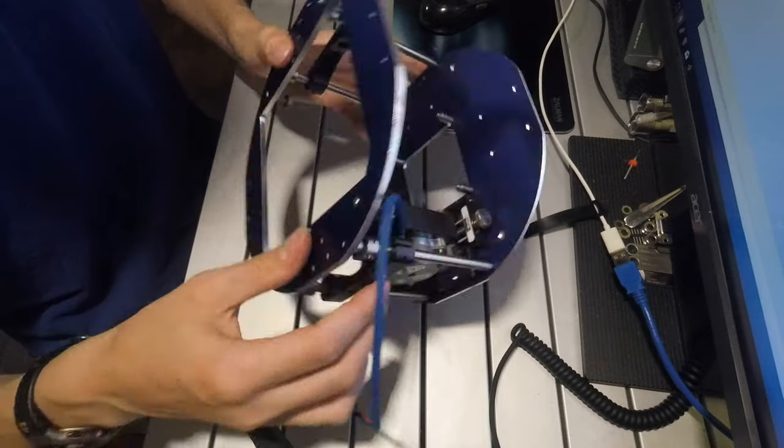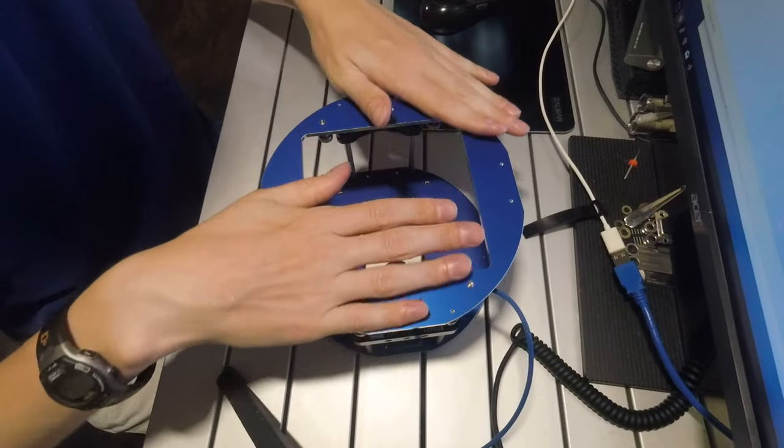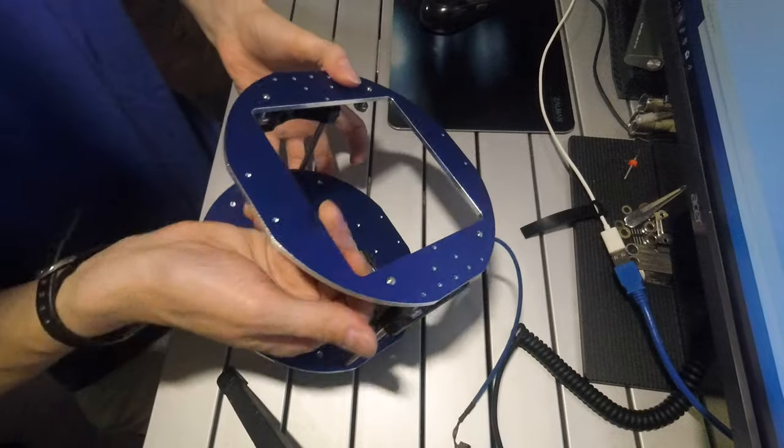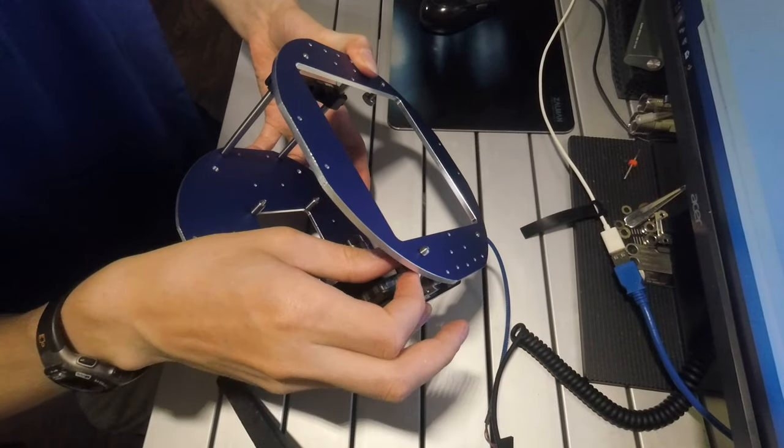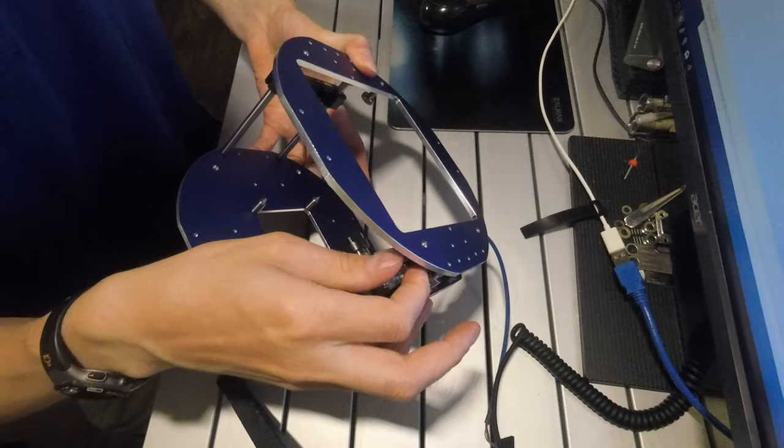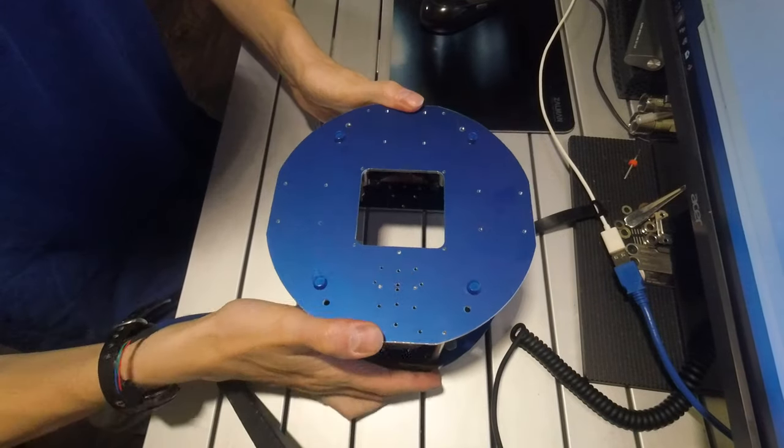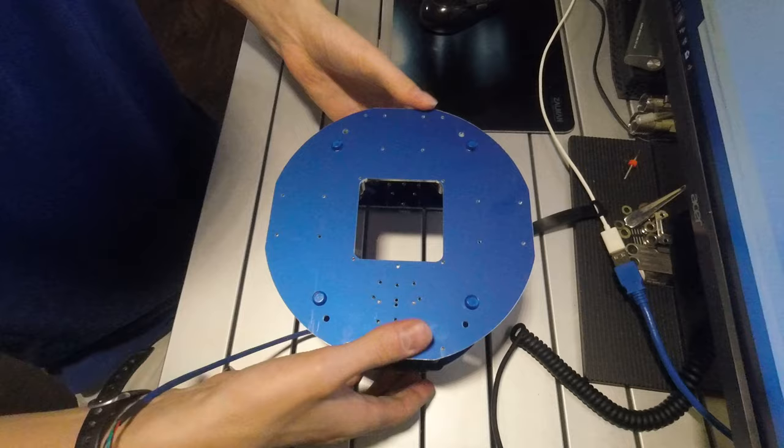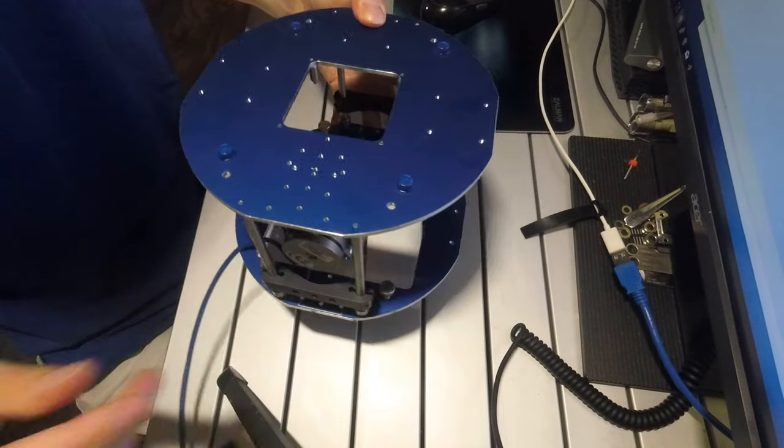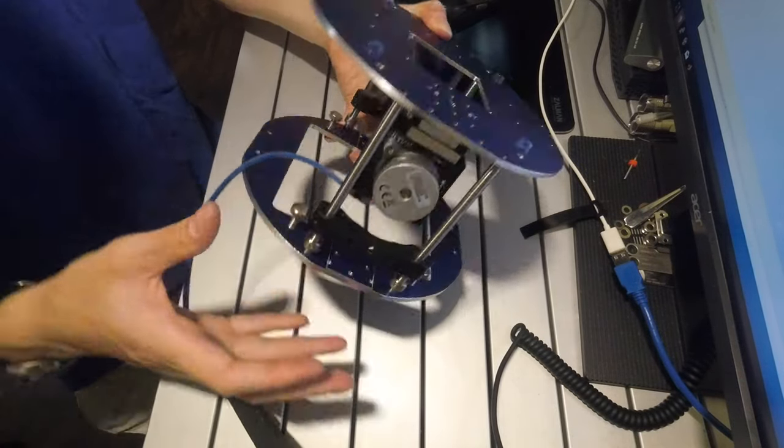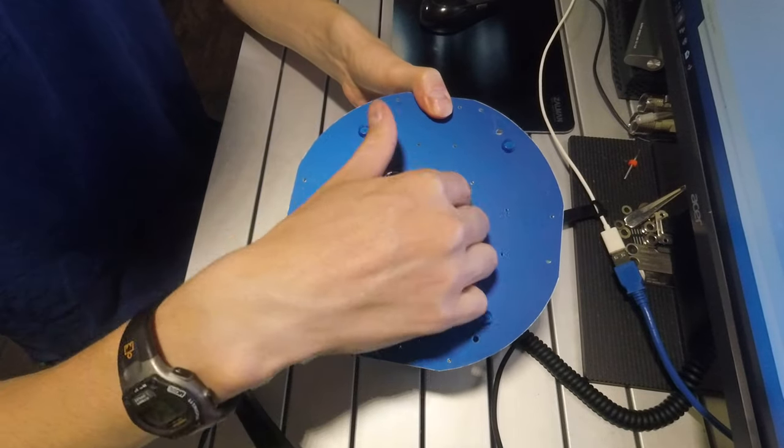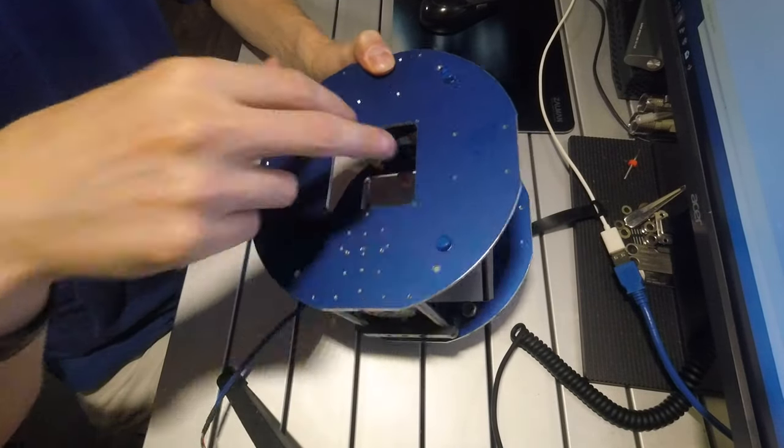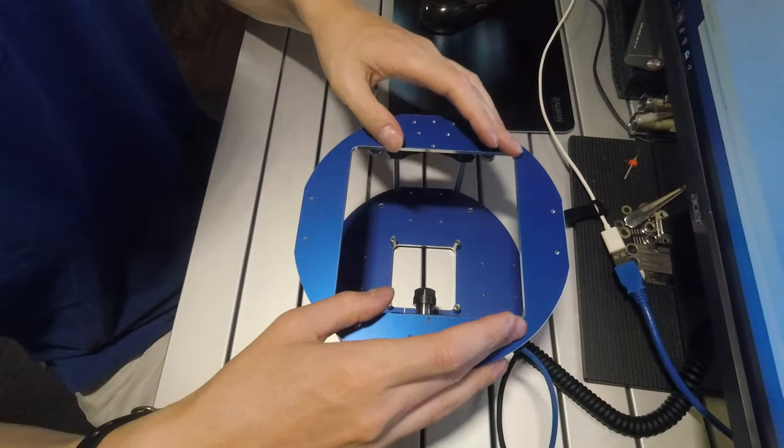Now the stage is constructed out of two layers. It has a bottom layer with some set screws which screw down to fix it into the base and a top layer which has some rubber feet which is pressed upward against the top of the Faxitron DX50. It has a cutout hole in the center for the x-ray beam to come down and a cutout hole in the bottom for the imaging sensor.